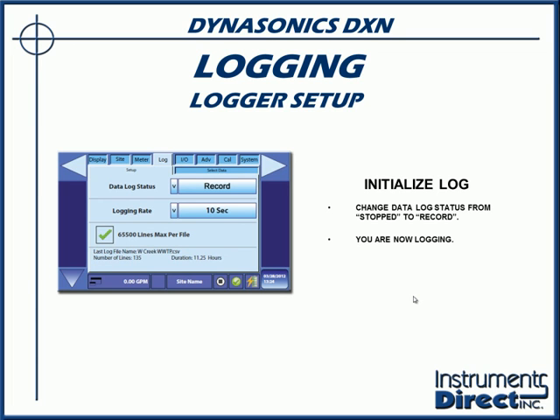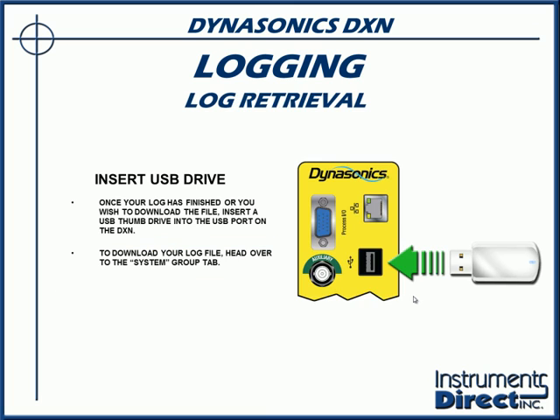Most people tend to use once a minute if you're doing an extended log, a daily log, a weekly log, or a monthly log. Remember, you get 1,440 data points in a day if you take a sample once a minute. So if you have a unique application, log as fast as you want, but you will get tons of data. So to retrieve the data, real simple, you plug a USB drive into the port on top of the box.